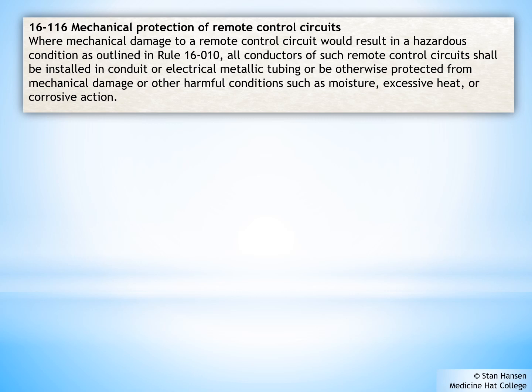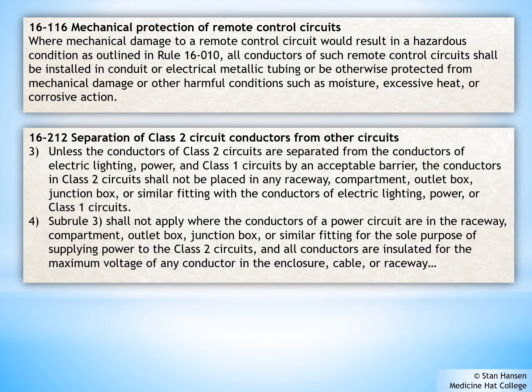When it comes to separation of Class 2 circuit conductors, we need to make sure that we have some sort of separation so there's no magnetic interference or any possibility of applying the wrong voltage to the wrong circuit. And since we have multiple types of circuits in heating equipment, we also need to make sure that they are adequately separated. Subrule 3 states that we cannot mix Class 2 circuits with any other circuits, and Subrule 4 states that the only time we can have a Class 2 circuit in the same enclosure as a Class 1 or power circuit is if it is for the purpose of supplying power to the Class 2 circuit. So in this case, it would be for a transformer. If we had a transformer inside an enclosure, then that's the only reason we can do that. Our wiring methods will depend on the equipment that we need to install in order to avoid these types of conflicts.